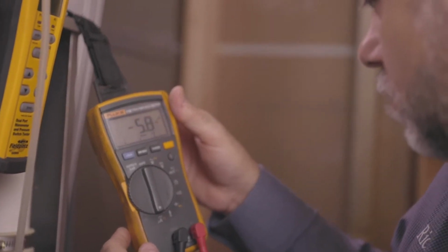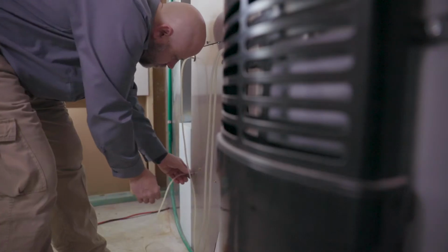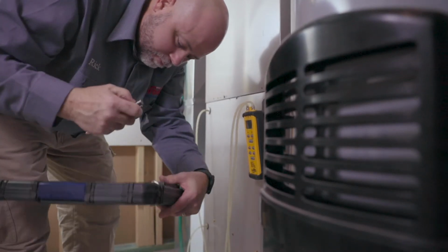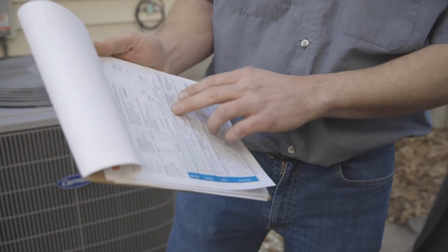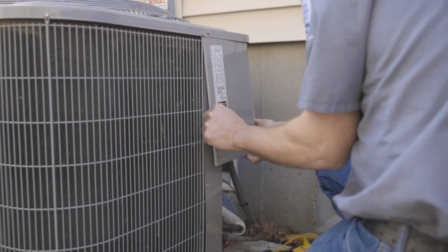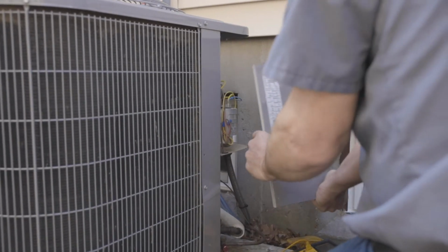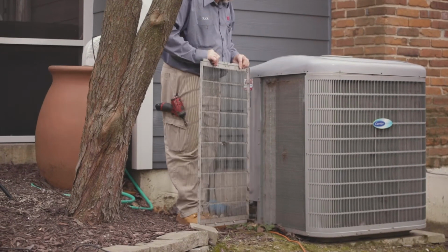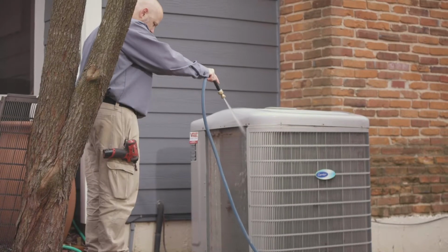We like to make sure that the return drop is the correct size for the blower, make sure that we're getting the correct static pressure. What that is going to do is it's going to give you all your SEER ratings. So your SEER rating is the rating that the manufacturer gives the equipment. And you noticed I said equipment, not system. So in order to gain that efficiency, your system all has to play a certain part in that. If you're installing a 20 SEER system, you may be only getting 15 SEER because your ductwork isn't sized correctly, or your air conditioner is clogged up really bad. A lot of it is with the installation, and a lot of it's upkeep and maintenance as well.